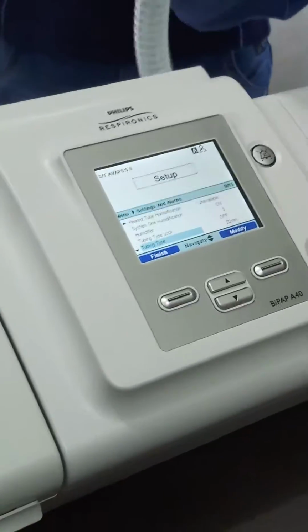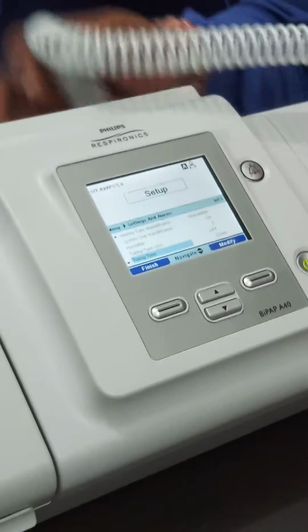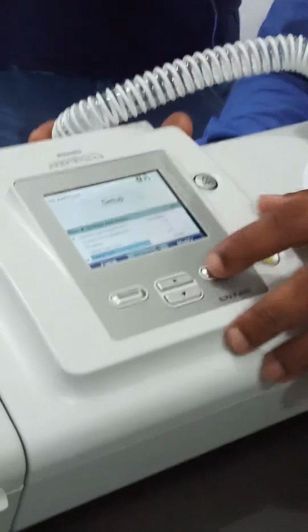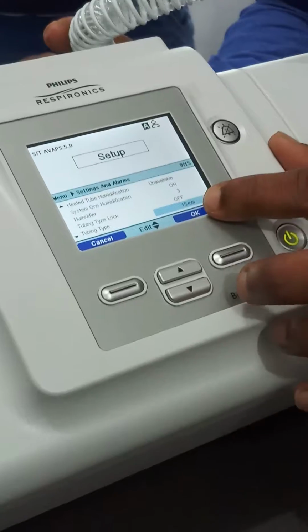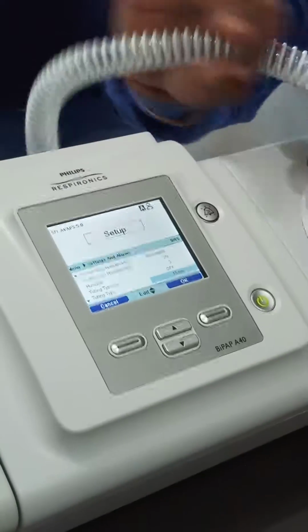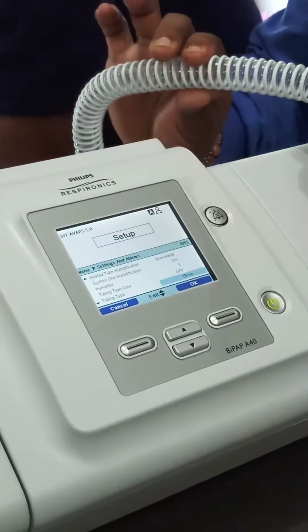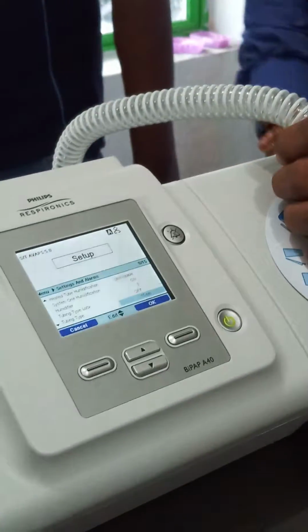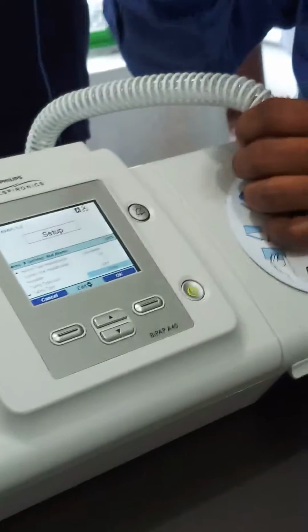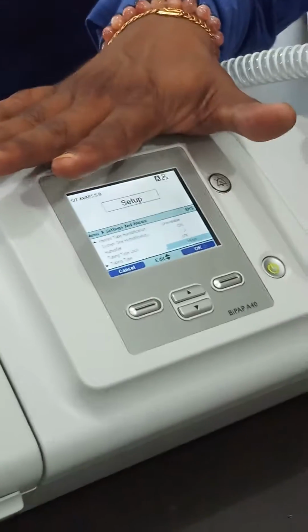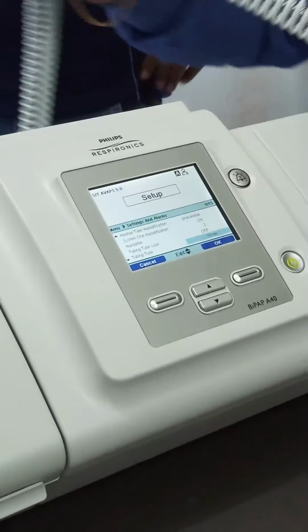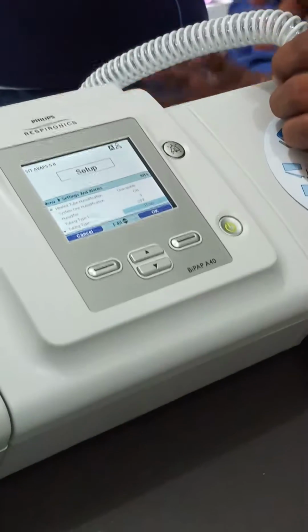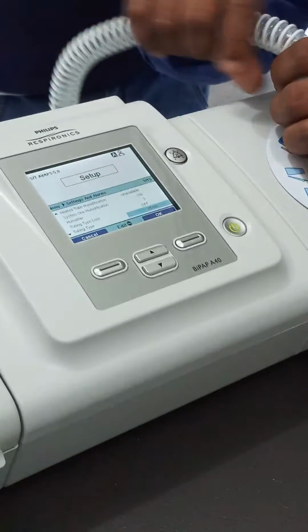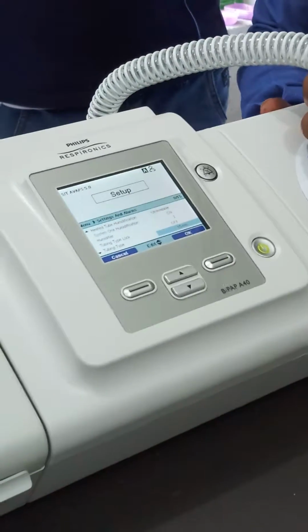This is 22 tubing, for the BiPAP level or CPAP level, I forgot to tell you. If a pediatric patient comes, you have to change to 15. Smaller dimension. Because the tender documents did not ask for a pediatric machine, we are not giving it, but as an additional advantage you can use it for pediatric. The dimension here is 22; you have to put 15, otherwise we can't use it.